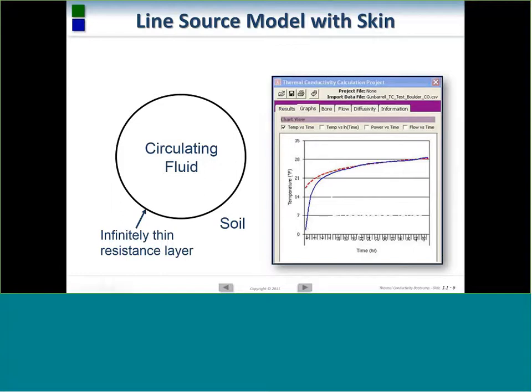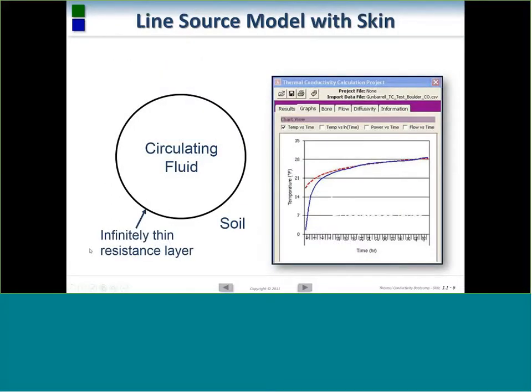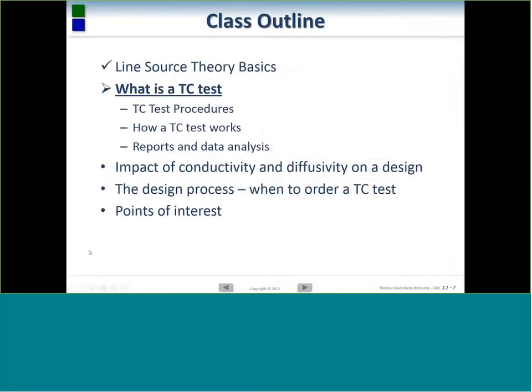And so that's what we see when we add heat in this breakdown period, which usually occurs in the first 10 to 12 hours of the thermal conductivity test before we get to more of the steady state condition towards the end. We're trying to make that bore go from this to this. And that is kind of how we bend reality of a bore, which has a three-dimensional makeup, into something much more linear, much less dimensional, or much more dimensionless.